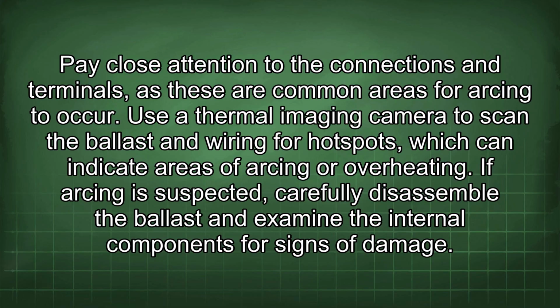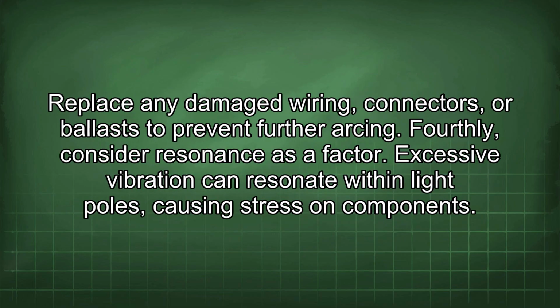Use a thermal imaging camera to scan the ballast and wiring for hotspots, which can indicate areas of arcing or overheating. If arcing is suspected, carefully disassemble the ballast and examine the internal components for signs of damage. Replace any damaged wiring, connectors, or ballast to prevent further arcing.